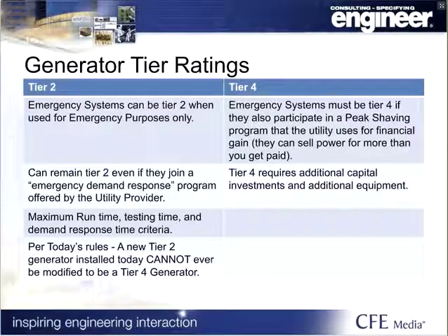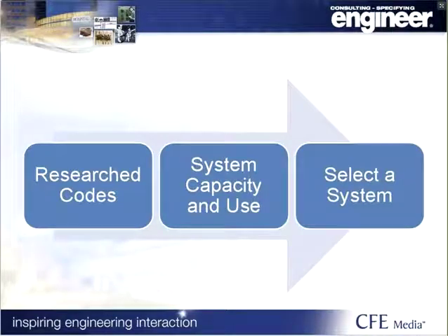So we talked a little bit about Tier 4 and about utility peak shaving programs. Right now there's a plethora of literature on the internet. I know Consulting Specifying has a couple of webcasts on generators and the EPA demand. EPA currently has a rule that says if you're using your generators as an emergency system, like a hospital function, they would not be required to be Tier 4. But if you're using your generators and participating in profit-making generator demand response, then you have to have Tier 4 generators. Tier 4 would basically mean that you're treating your exhaust emissions and putting out clean exhaust. And it does add cost and does add space to your room. And now back to you, Rob. Thanks, Jim.